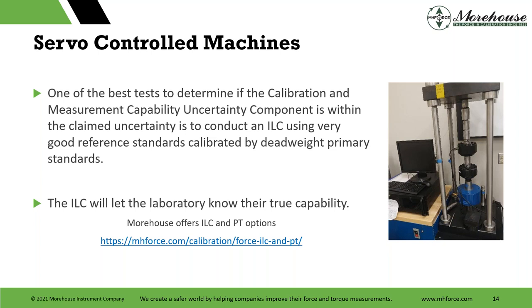If you have a machine, we've done all the Excel templates and everything else where you can use these templates to do your own PT, which basically is: we calibrate a load cell in dead weight. We ship it to you. We know what the value should be. You put that load cell in your machine. You record the outputs, and then you compare the outputs against what we got calibrated in dead weight. The sheet will give you an EN ratio and a Z score.